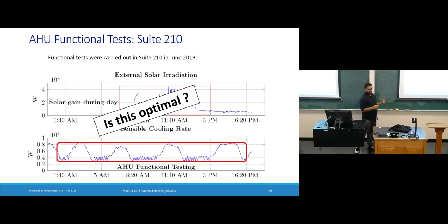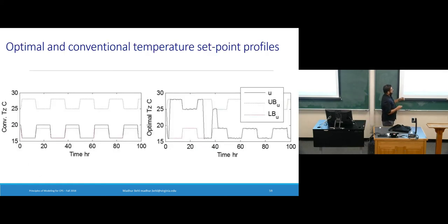Let me give you the results first, then show how to actually do this. On the left hand side you have the zone temperature set point. The green and red are the upper and lower limits of the set point over a few days - maybe 5 days or so. You can see that when your zone is occupied, you have a tighter comfort band; when not occupied, the band is larger - the band being the difference between lower and upper limits. The black line tells you what the zone temperature was during business as usual operation.